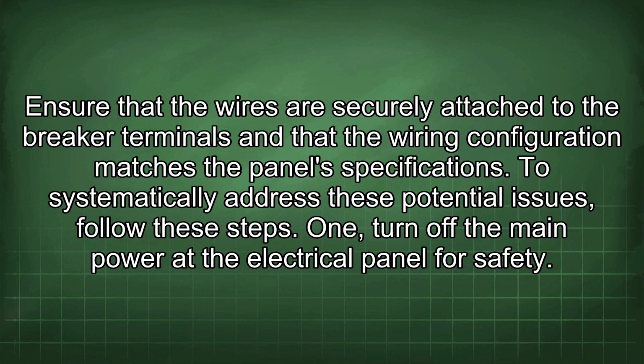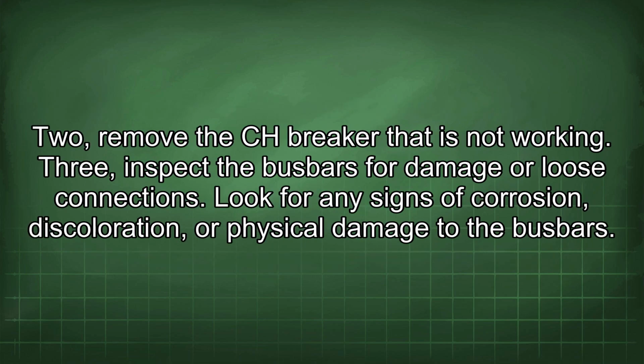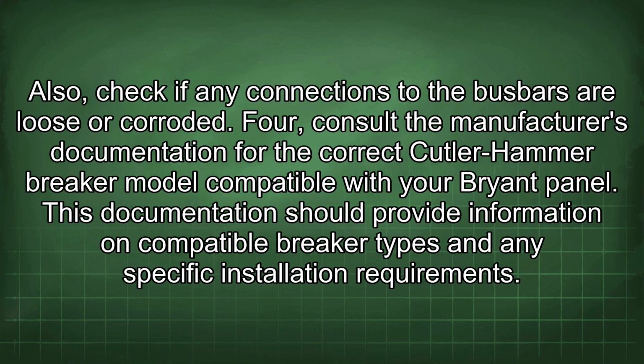To systematically address these potential issues, follow these steps. 1. Turn off the main power at the electrical panel for safety. 2. Remove the CH breaker that is not working. 3. Inspect the bus bars for damage or loose connections. Look for any signs of corrosion, discoloration, or physical damage to the bus bars. Also, check if any connections to the bus bars are loose or corroded.